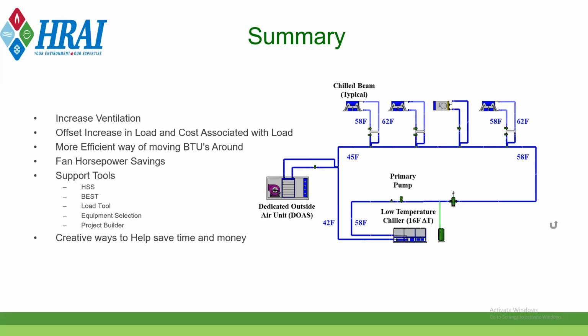In this case, being decoupled, that pump really just needs to overcome the head of the distribution loop. And then the local zones are being serviced through zone pumps in this particular case, and a one-pipe system, but could still be zone valves if it's a two-pipe distribution system.